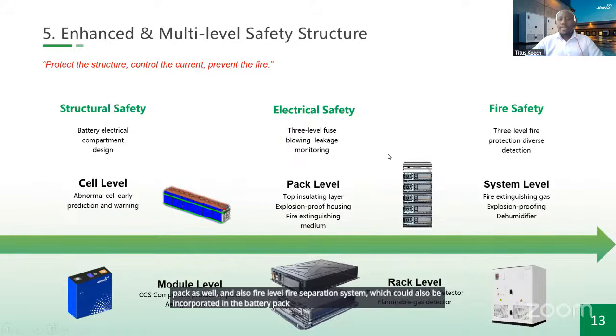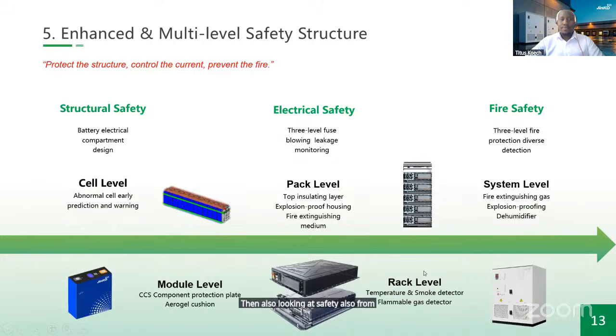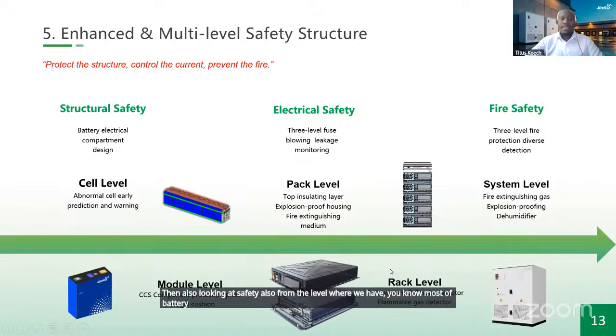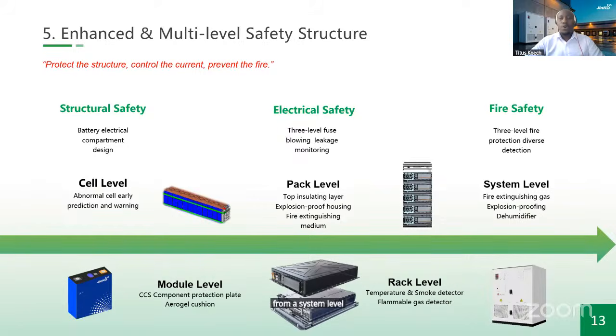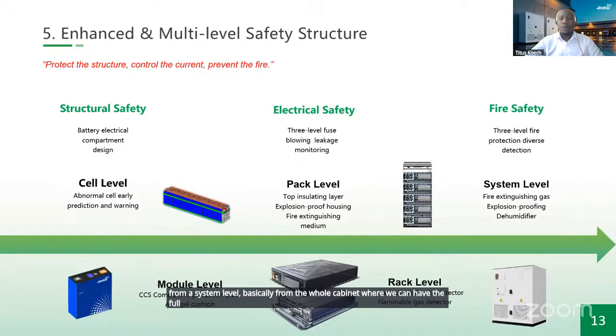Then also looking at safety from the rack level, where most battery energy storage systems incorporate temperature and smoke sensors, or elements of the fire suppression system. And also from a system level, the whole cabinet, where we can have the full fire suppression system.